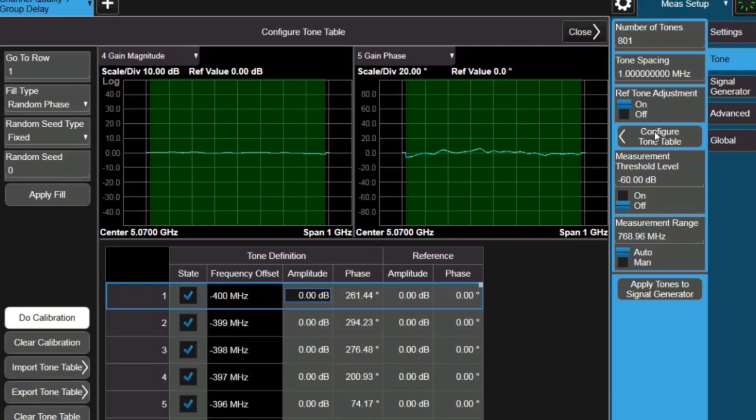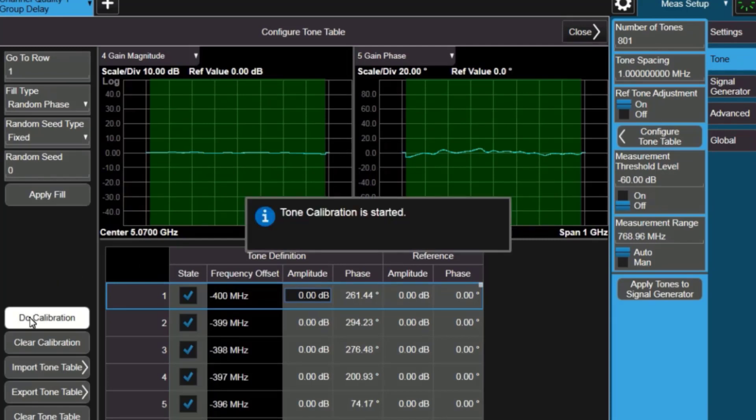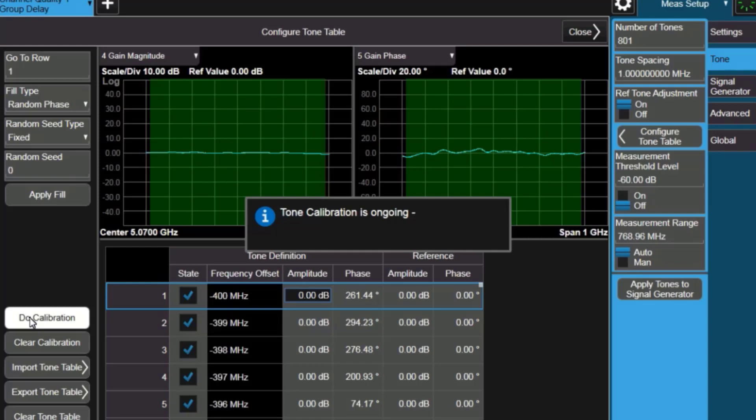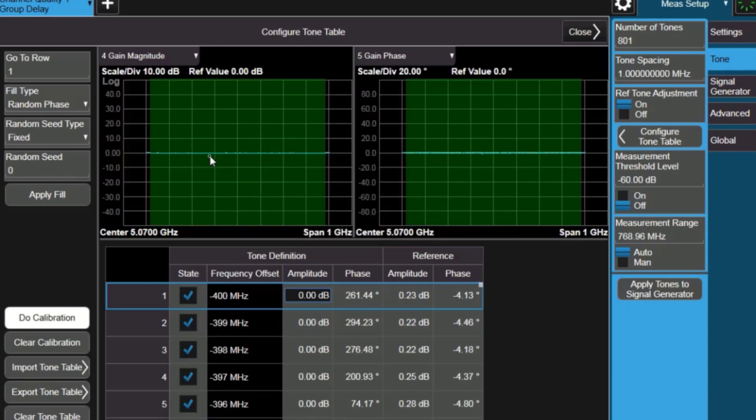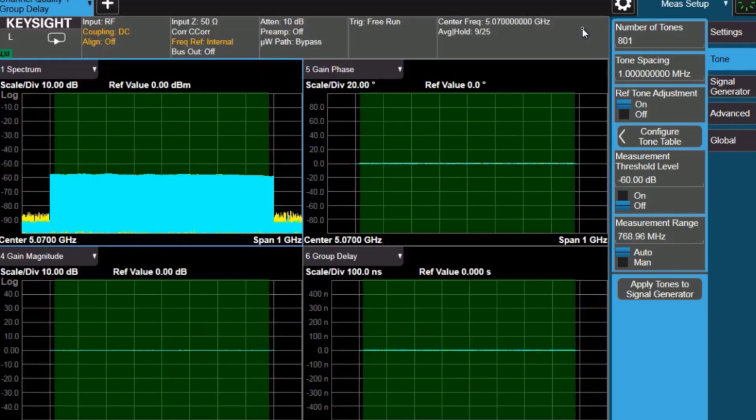We can get rid of the ripple by doing a kind of calibration. So we say do calibration, and it'll start by measuring the tones that it sees in the receiver, and then creating a calibration file that compensates them so that the new measured values will be compensated by any gain, amplitude, or phase deviation that we're going to see. When it's finished, we can see in the table how much amplitude and phase correction it's applied.